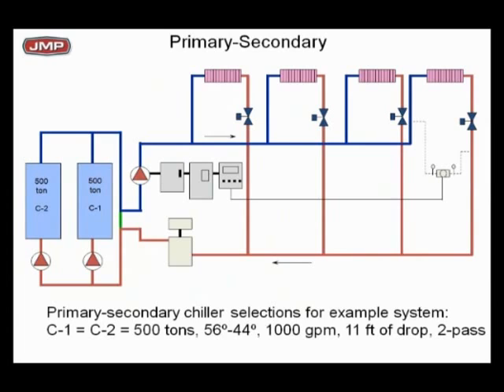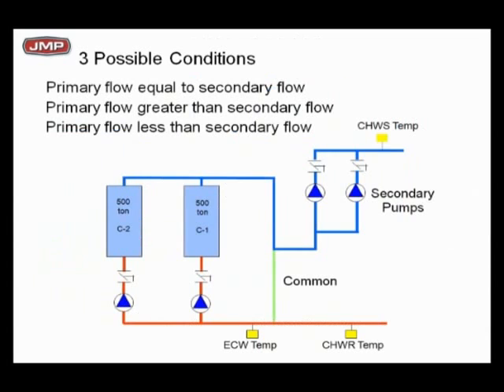Look at my green common pipe, primary, secondary. I've got a secondary pump that's variable flow, two-way valves on the coils, and that flow is going to vary. Let's see what happens as I vary the flow on the secondary loop and stage chillers. Remember to load this chiller up. Design is 44 supply, 56 degree return water, 12 degree delta T. So let's just take a look.